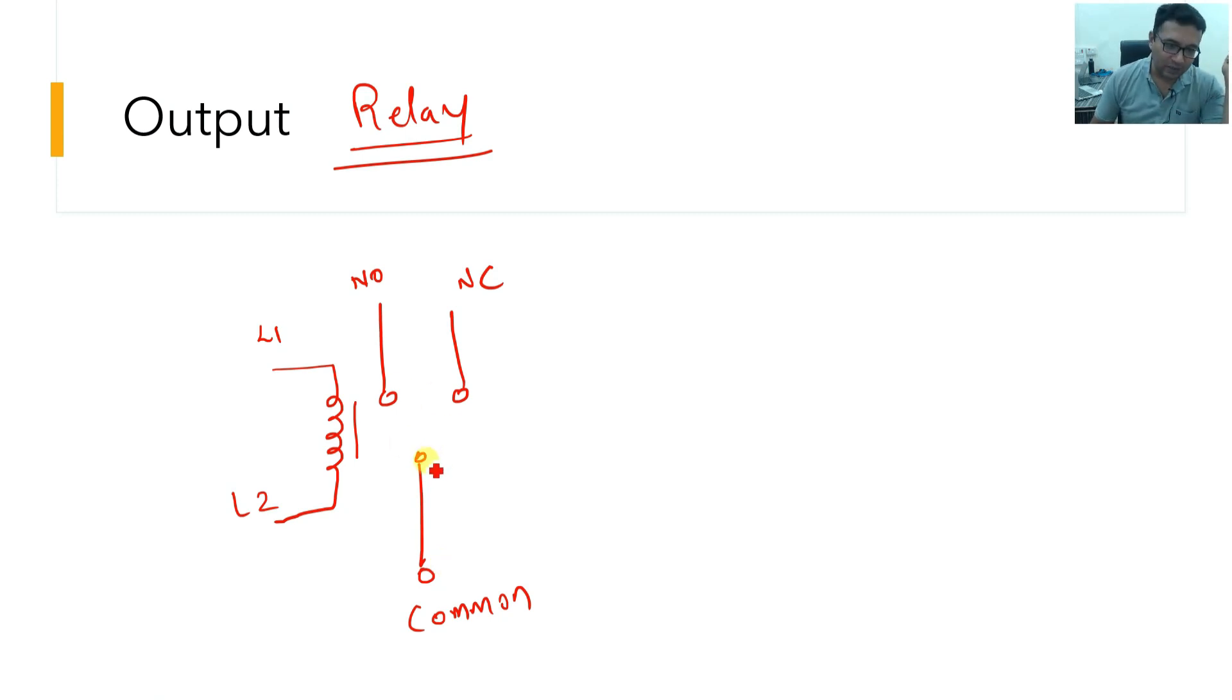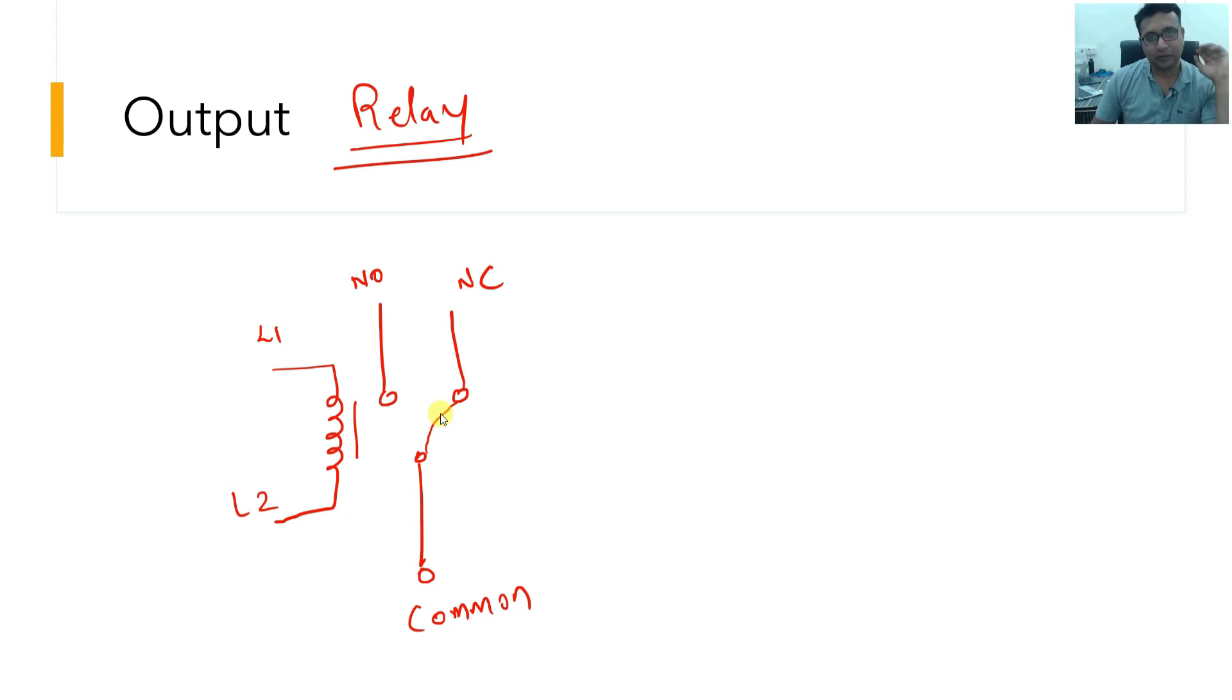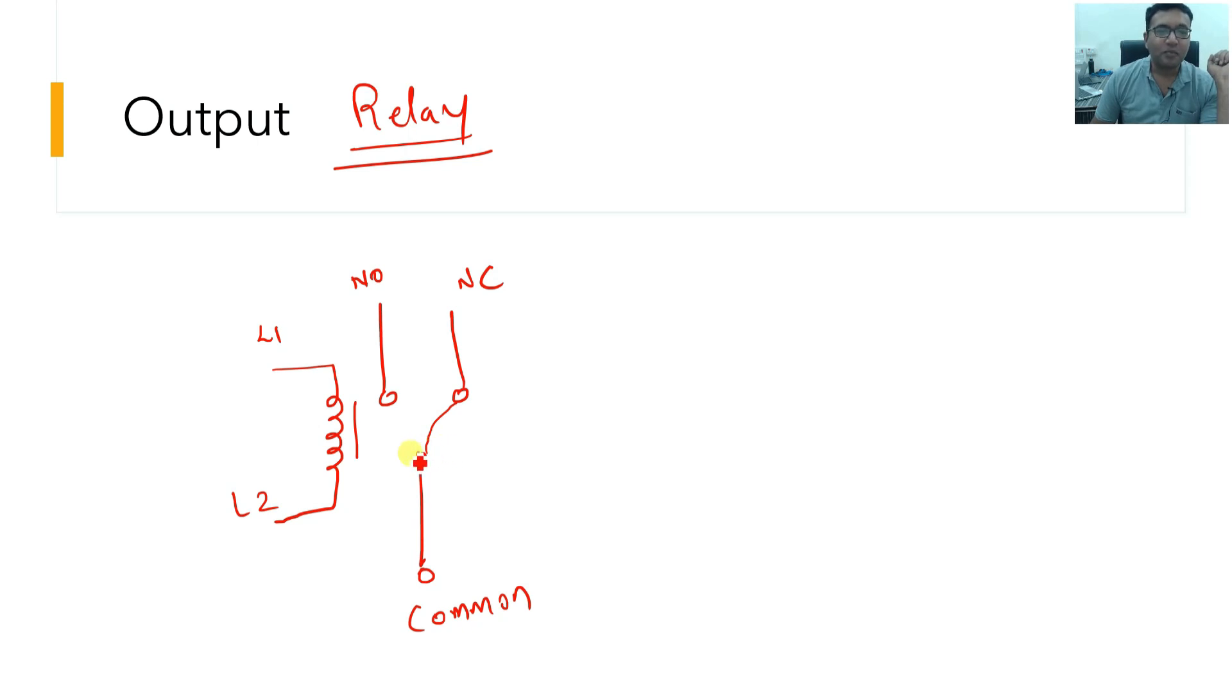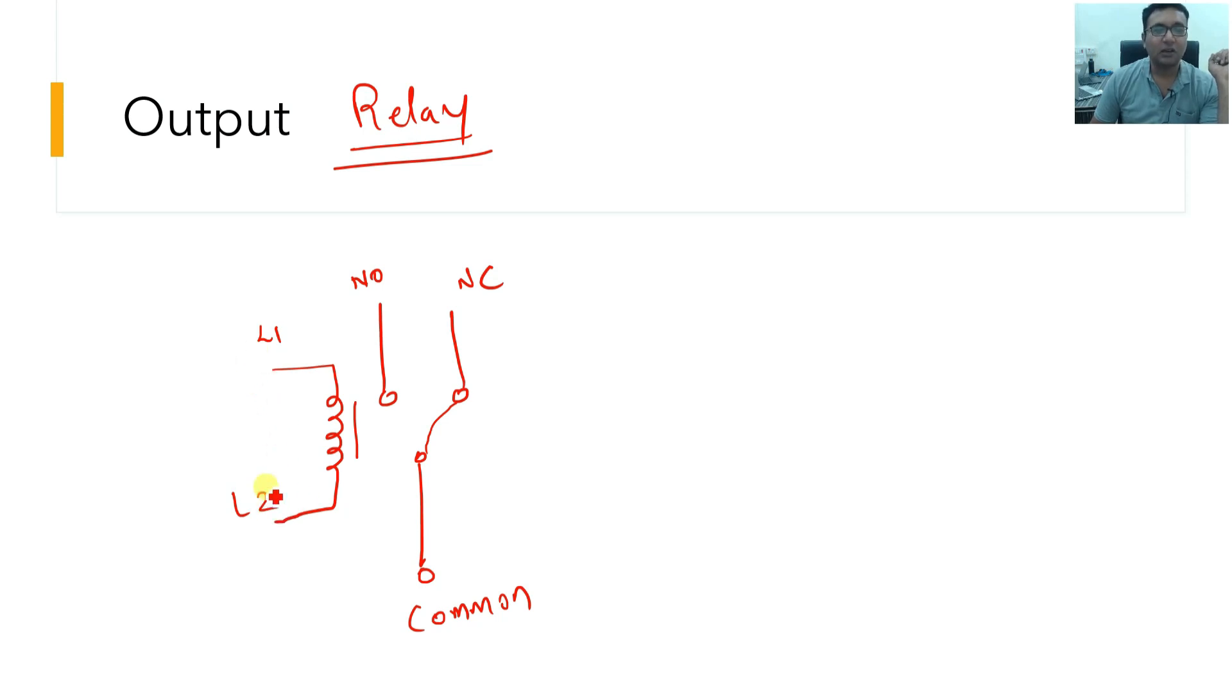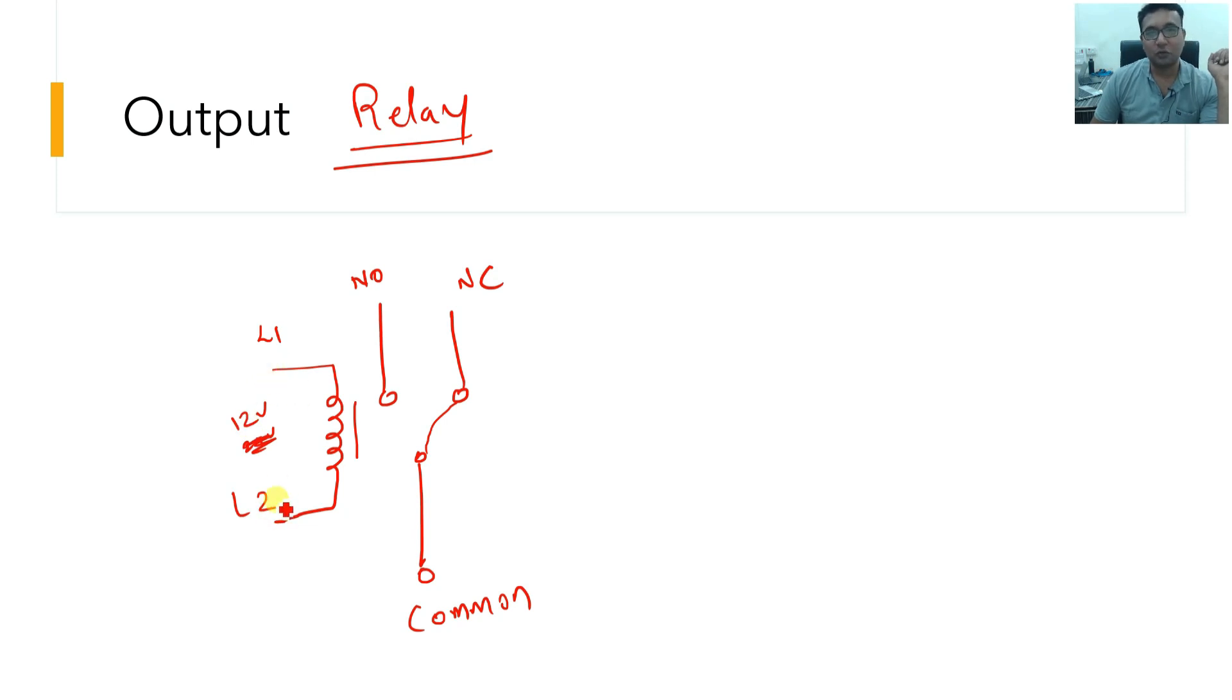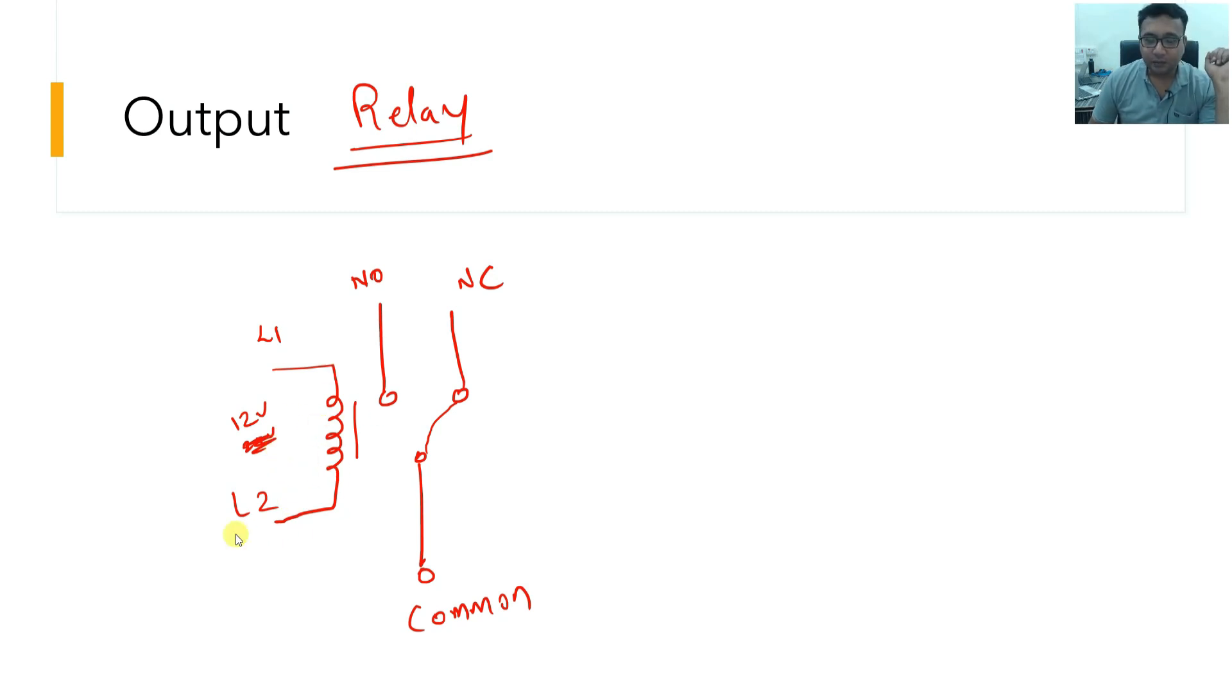There is a small spring attached to this common terminal, which keeps it connected to NC all the time. When the relay is kept on a table, when the relay circuit is powered off, there is no voltage given, no excitation given, the common is connected to NC using a spring pull up. Now, what happens is, when you give a rated voltage to L1, L2, there is no polarity to it. You can give positive here, negative here or negative here and positive here. There is a rated voltage for the coil, let's say it is a 12 volt coil or 24 volt coil.